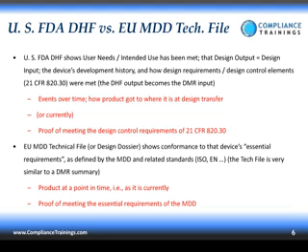When we talk about the design history file for devices, it's a requirement of the GMPs for devices, 21 CFR 820, specifically 820.30, design control. This was added to the GMPs back in 1996-97, because the FDA recognized that a lot of problems with products in the field were a result of design problems, and on the basis of their audits, they found that many of the design problems were caused by poor control of changes during the design phase. So they implemented this new requirement back in 96, 97, and gave companies a year to transition in order to address that. So bear that in mind as we go through this discussion.